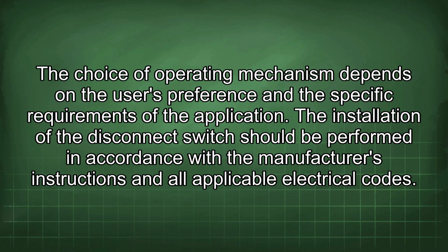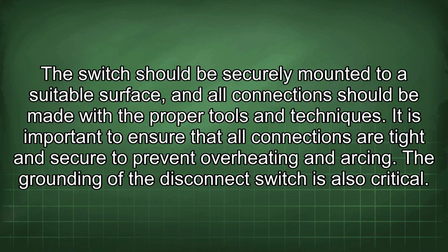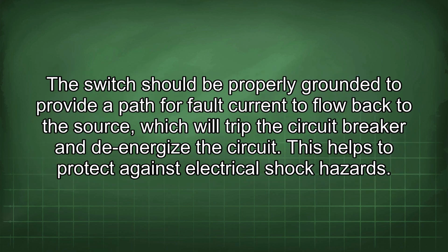The installation of the disconnect switch should be performed in accordance with the manufacturer's instructions and all applicable electrical codes. The switch should be securely mounted to a suitable surface, and all connections should be made with the proper tools and techniques. It is important to ensure that all connections are tight and secure to prevent overheating and arcing. The grounding of the disconnect switch is also critical. The switch should be properly grounded to provide a path for fault current to flow back to the source, which will trip the circuit breaker and de-energize the circuit. This helps to protect against electrical shock hazards.